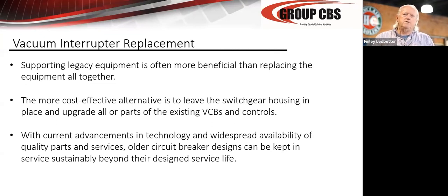That's if it's manufactured correctly, it's seen no thermal overload, and everything operates correctly. And we see interrupters that live in excess of that, okay? I'll be honest with you, Mitsubishi interrupters live a hell of a long time. Their leak rate's very low. Some of the other manufacturers have low leak rates. Some have very high leak rates. And the newer manufactured interrupters have much higher leak rates than they had 15 or 20 years ago. So getting that leak rate information, or just simply planning to replace the interrupters at, say, 30 years, is a really good idea. Now, in critical circuits, I would be very cautious going beyond that period.